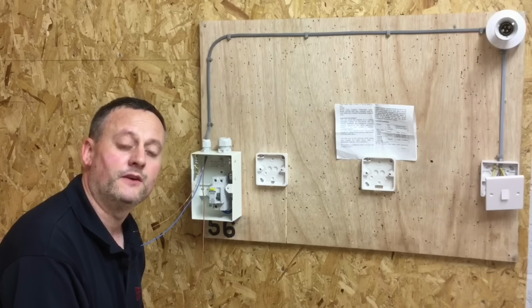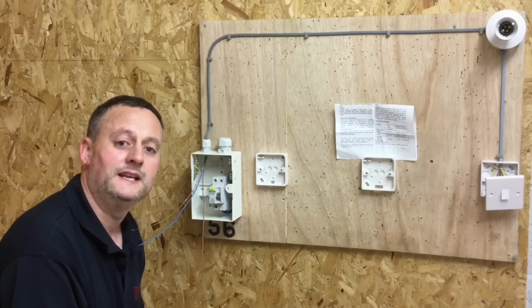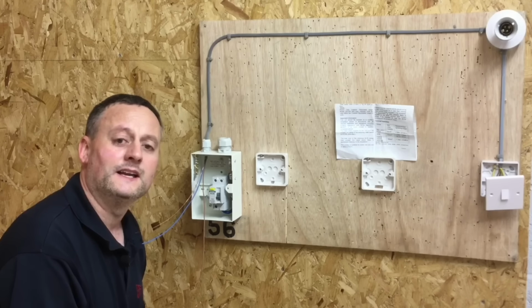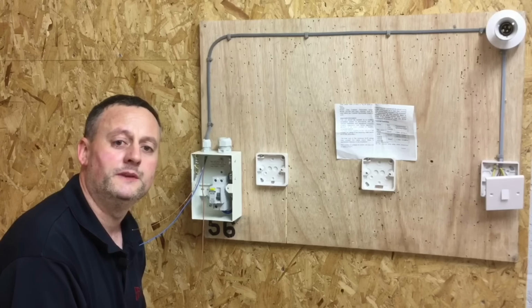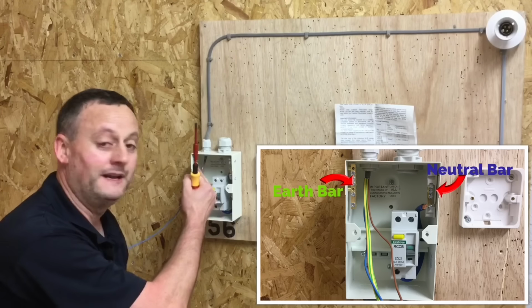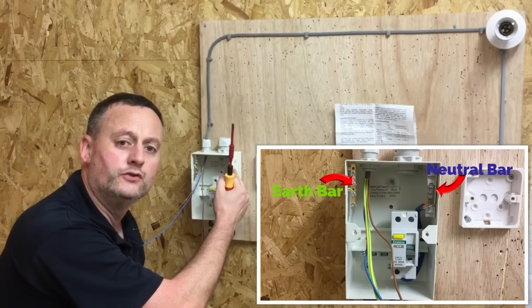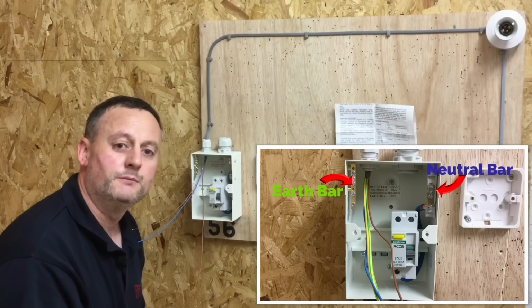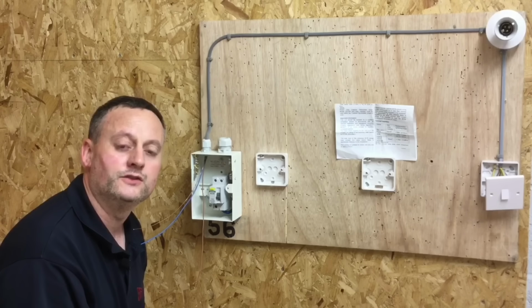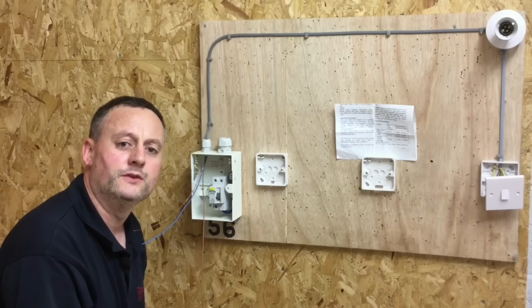Let's see how we're going to identify those conductors and how we're going to dress them neatly within the consumer's unit, in order that there's enough spare within there in case the termination becomes damaged or the consumer unit is changed in the future and our connecting points are not quite in the same place. So at the minute we've got the earth bar on the left hand side, neutral bar on the right hand side. In the future the board may be upgraded, maybe to a larger distribution board, and we want to make sure we leave enough cable inside the consumer's unit that we can reposition them in the future.